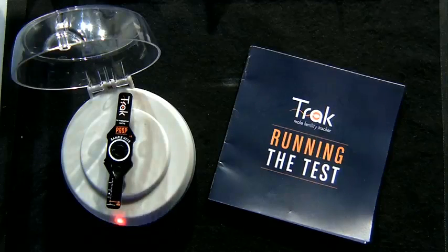I'll quickly show you how it works. This is a device with disposable test cartridges. A man simply collects a sample, puts a few drops into the device, closes the lid — and if you can see that, it's spinning. What we are doing is using centrifugal force to isolate the sperm cells and give the couples a reading of sperm count, measured in millions of cells per milliliter.